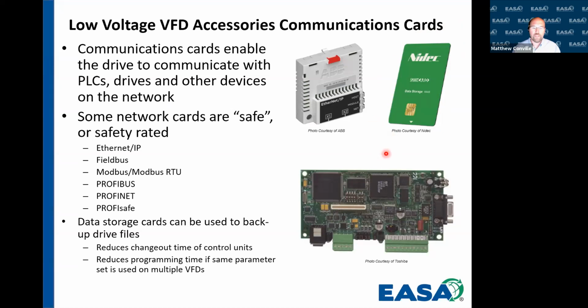So you might be looking at, let's say, $75 to $200 or so for a smart card or compact flash card. But in the middle of the night, whenever somebody has to do a drive change out, that expense is very small in comparison to having to call a bunch of people in and going back to retune the drive. You can plug in the smart card, you can upload the parameter sets, everything can be the exact same as it was, assuming that the last file got uploaded to the smart card, and you're back up and running and going.